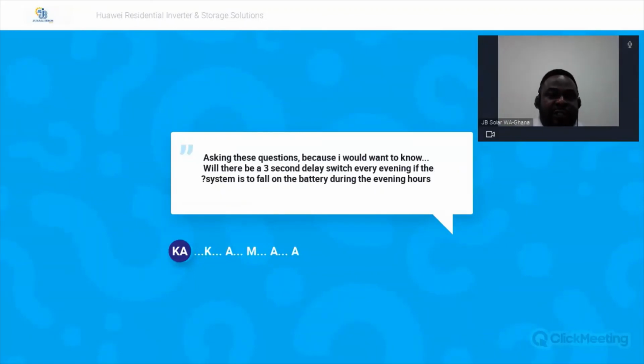I hope I am doing my best to answer your questions. Kwame again is asking: will there be a 3-second delay switch every evening if the system is to fall on the battery? No, that is seamless. You don't even realize it. When the system is switching from inverter control to battery, that is seamless, and there is no flicker at all. It's just like your load in the house is all supplied by the inverter, and then at a point in time your load goes up, so now the inverter is asking for some load to be supplied by the grid. It's seamless, it's automatic, you don't even know it.